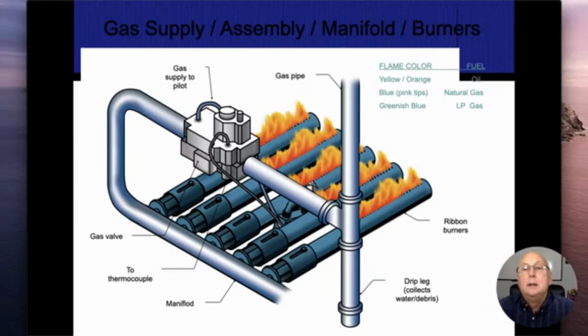Don't be surprised if you see test questions on that. Natural gas, typically going to be blue, and there's going to be some pink or orange tips to it. LP is going to be more of a greenish tinge blue. When we're dealing with oil, it's going to be either orange-yellow or yellow-orange that's mixed in there. But most of the stuff we're going to have around here is going to be natural gas or propane. So it's going to be blue or green when we're dealing with it.